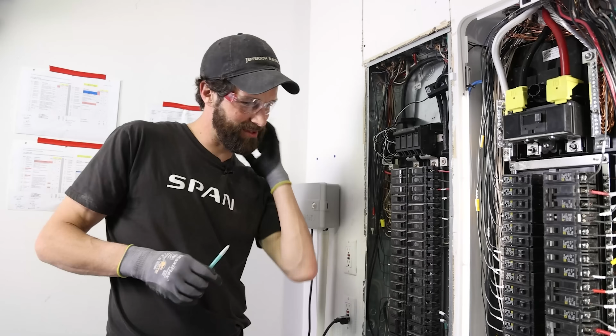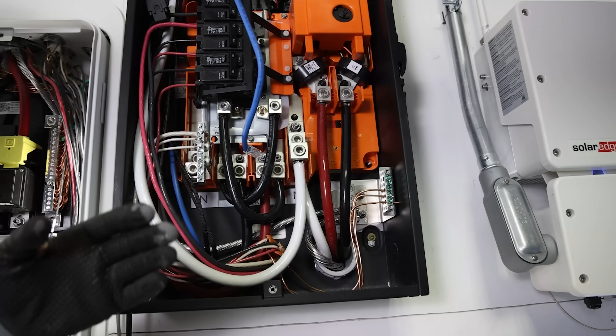We've got CTs on the hots here in the dummy panel. There's no tech in this panel other than the breakers, but the CTs are connected to the Tesla gateway. The Tesla gateway is kind of a central component from an energy flow standpoint in this equation, because the CT's current transformers indicate to Tesla what the energy draw here is. Tesla's connected to SPAN, so we've got insights. Tesla's got the CTs on the dummy panel, so we know what the draw, the consumption is. Tesla has the SolarEdge inverter landed in it, and it's connected to the power walls. So this is kind of the brain box in this case.